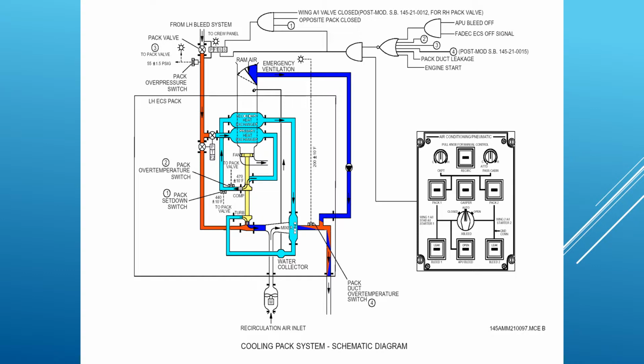There is another temperature switch. Actually, there's a temperature switch just as the air comes through the mixer, through the core of the condenser before it goes into the cabin. It's measuring the duct temperature at that point. If the temperature is 90 degrees C, that will actually also cause the pack to shut down.